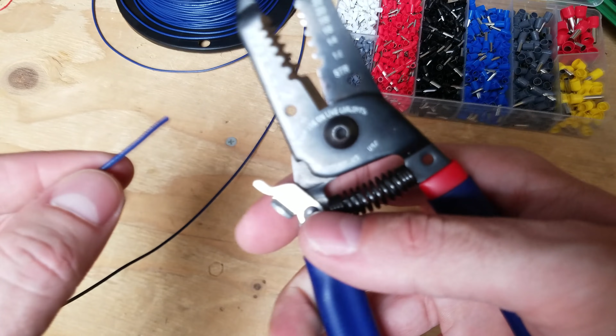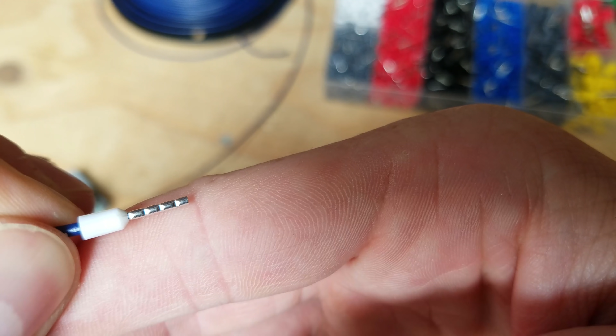Take your wire strippers and strip off some insulation the length of the silver part of the ferrule, then twist your wire a bit and put the ferrule over the exposed wire. You should just be able to see the wire at the end—you don't want it sticking out, but you want it going the entire way through the ferrule. Then insert this into the crimp tool and crimp it down.